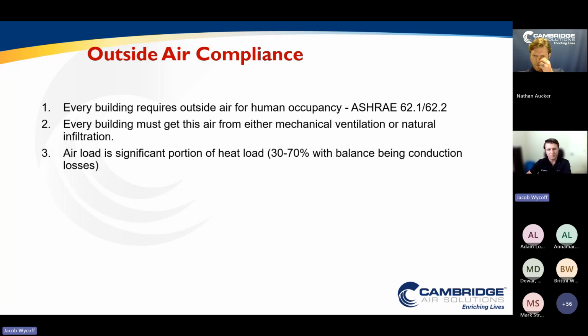When we talk about heating these spaces using 100% outside air, it becomes much simpler to talk about it by separating the air load, which is that outside air that needs to be heated as it comes in or when it's in the facility, and the rest of that heat load being the conduction losses, the skin losses through the walls and roof of the building. Those can vary between about 30 to 70% each.